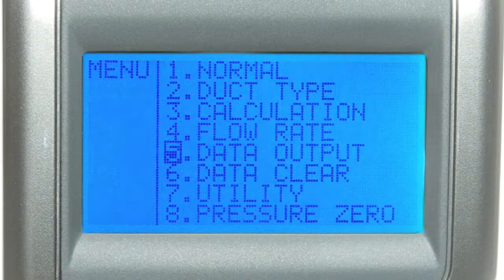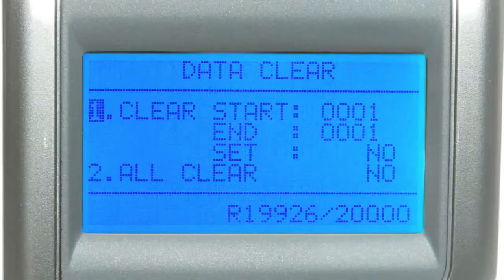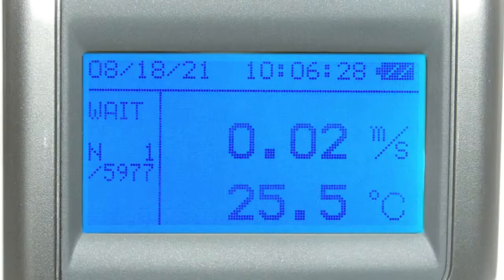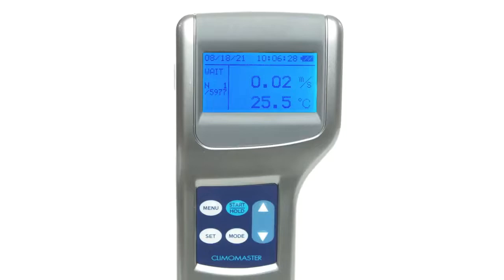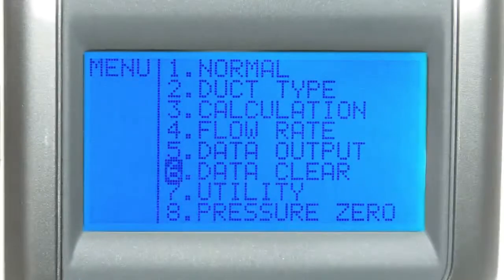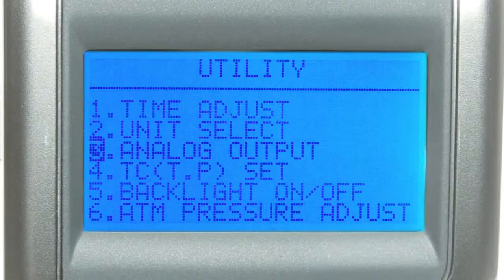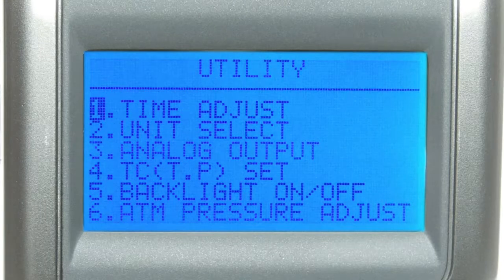To delete all data from the device, navigate to the section labeled Data Clear in the main menu. From here, you can define the range of pages you'd like deleted from the Climomaster's memory, or you can simply set All Clear to Yes and press Set to delete everything. To print out stored data, connect the printer cable to the serial communication terminal located on the side of the device. You can download the data stored in the Climomaster to your PC via the USB port and optional PC software. The 6501 CE model offers 0 to 1 volt analog output. To output data via analog output, navigate to the Utilities section from the main menu and select Analog Output. Beyond configuring the analog output of your device, the Utilities section of the Climomaster offers multiple ways to customize your device. You have the option to adjust the internal clock of the device, select the default units used across your device, and the option to turn the LCD backlight on or off.